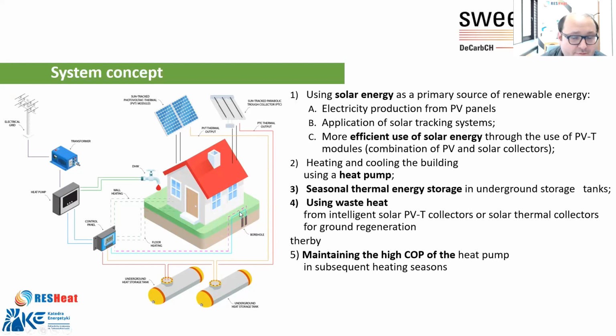Often there is a problem where heat is drawn from the ground without regeneration, causing the heat pump COP to decrease in consecutive heating seasons. We try to avoid this by using ground regeneration.